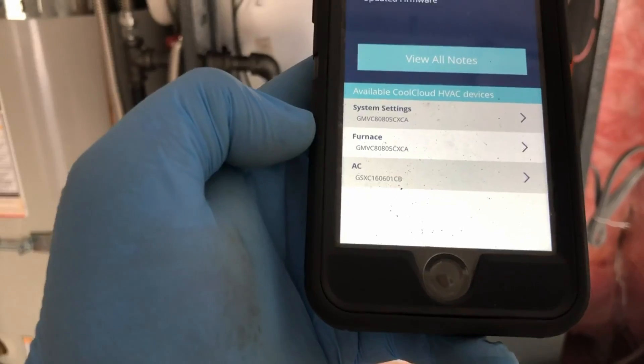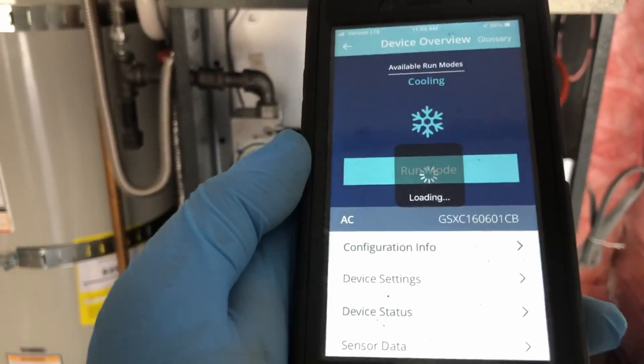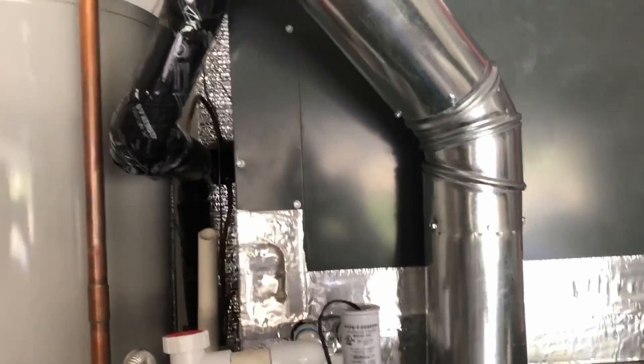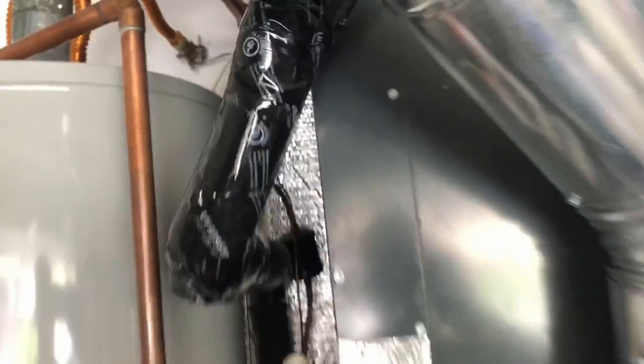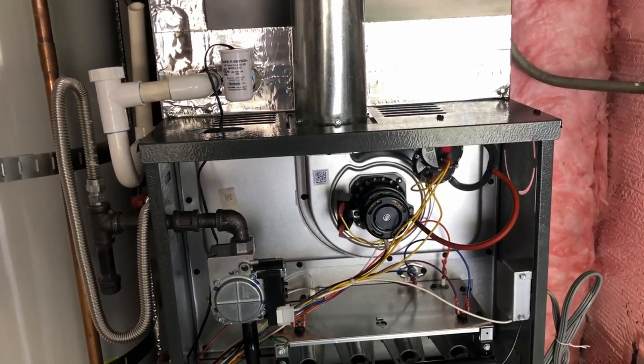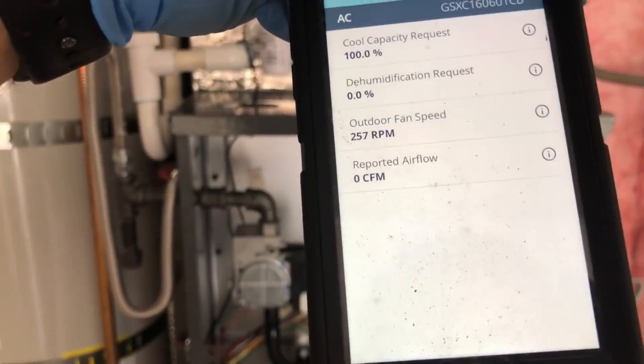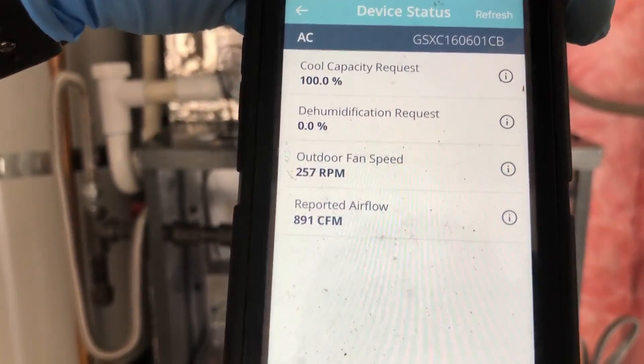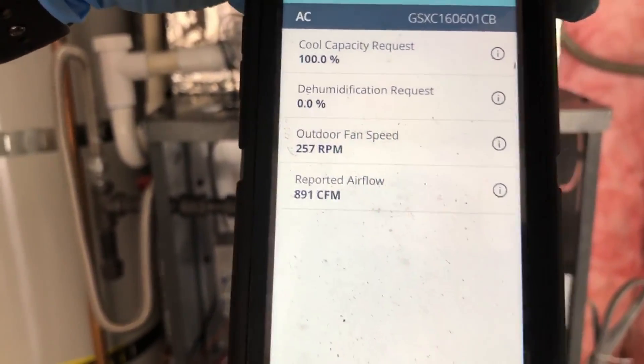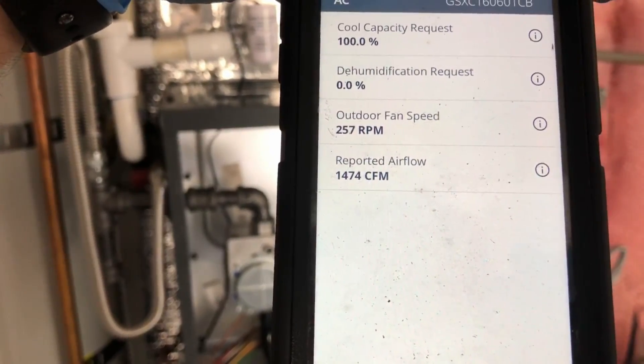Now if we want to test the AC, we go to AC, select the snowflake, and hit run. Capacity we want — we're going to do 100%. The compressor just came on and I can hear the refrigerant moving through the pipes. The blower will come on shortly. Looking at the data: outdoor fan speed, RPMs, and then the CFM. The blower hasn't come on yet because we have it delayed. After hitting refresh, we're at 891 CFM as it ramps up. Refreshing again — still slow speed — and now it's already ramped up to 1474 CFM.